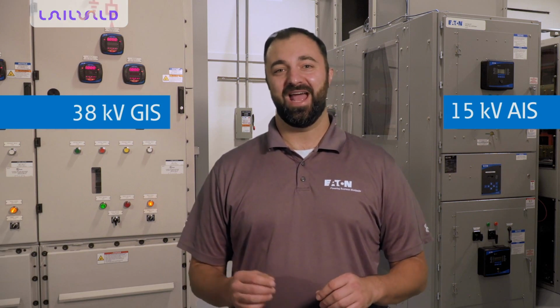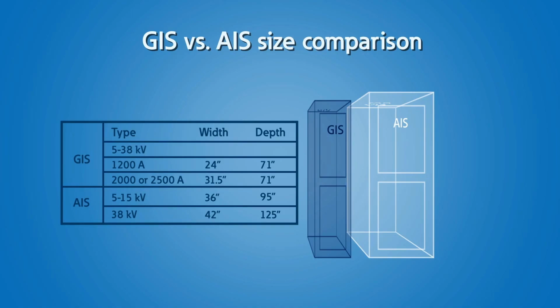Looking to my left, you will see a lineup of air-insulated switchgear, and to my right, gas-insulated switchgear. As previously noted, one major difference between AIS and GIS is footprint. For the 5 to 38,000 volt GIS structure shown, the 1200 amp GIS structure is roughly 24 inches wide, and the 2000 or 2500 amp structure is roughly 31.5 inches wide. The 5 to 15 kV AIS switchgear here has a common width of 36 inches for all bus ratings. AIS switchgear at 38 kV is typically a single high construction and is 42 inches wide.